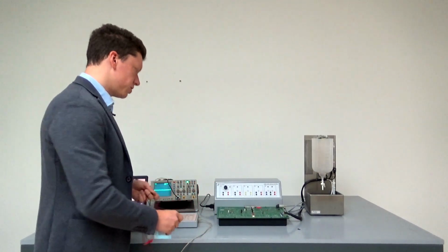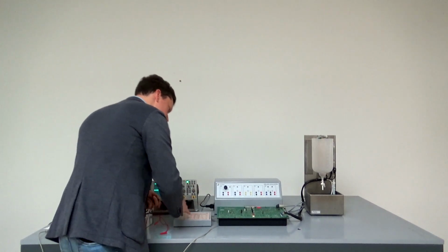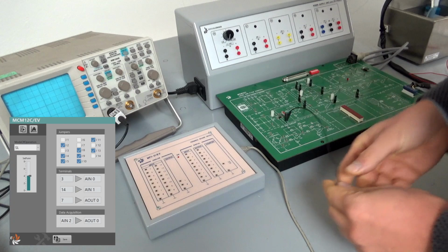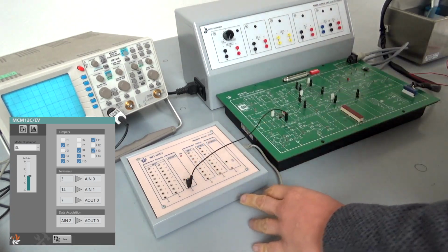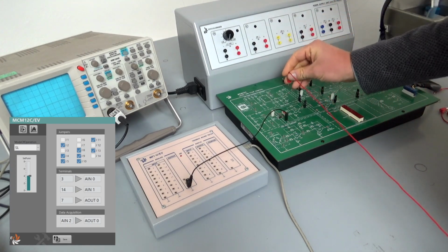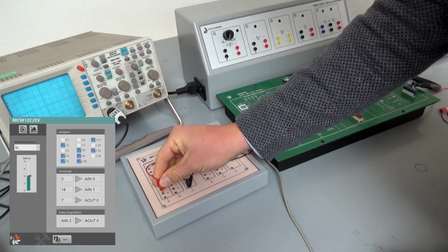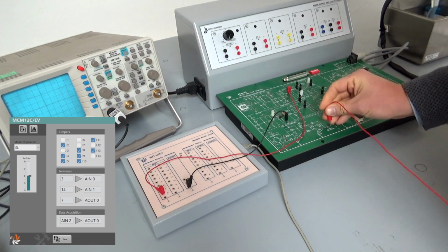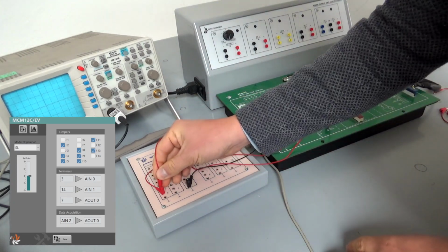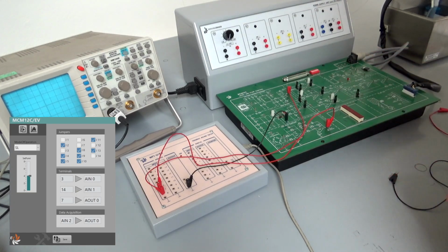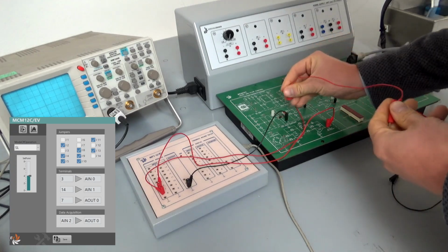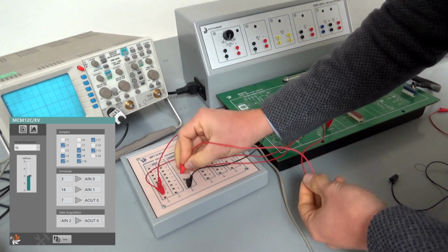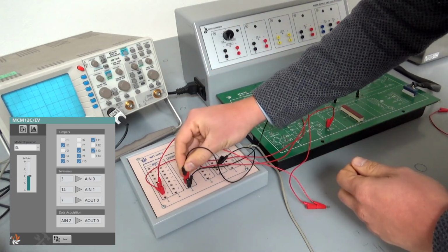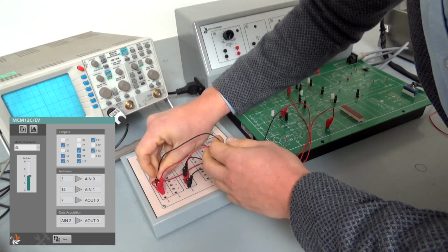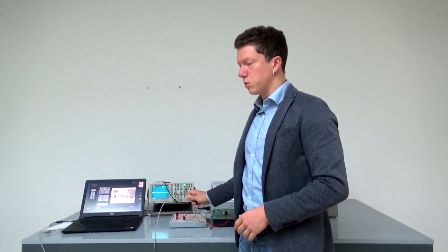So now let's perform the cable connection between the unit and the DAQ board. So first the ground connection, common. Then you got the output of the flow signal converter to terminal number A0. Then you got terminal 14, which is the output of the level transducer in 1. And then you got the output wired to an input here. And at last you got the output 0 wired to the input 2. At last, the DAQ board has to be connected to the PC via the USB cable.